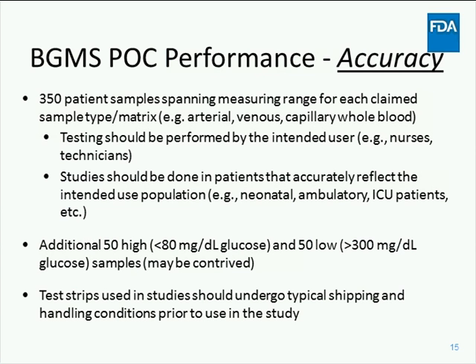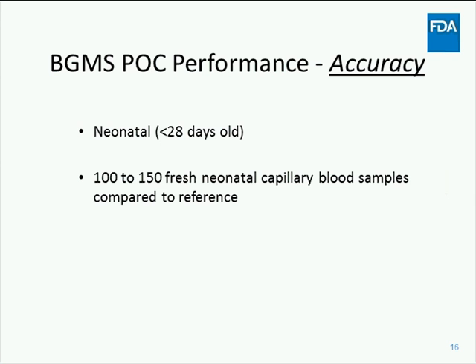These samples should span the glucose measuring range for each sample type and be compared to a comparator method. If natural samples with concentrations at the extreme ends of the measuring range are not obtained during the study, then additional samples may be contrived by spiking or glycolysis to obtain an additional 50 samples with high glucose concentrations greater than 300 mg per deciliter and 50 samples with low glucose, less than 80 mg per deciliter. Another difference from the studies that we currently see is the recommendation in the guidance that the test strips used in these studies have undergone typical shipping and handling conditions prior to use in the study.